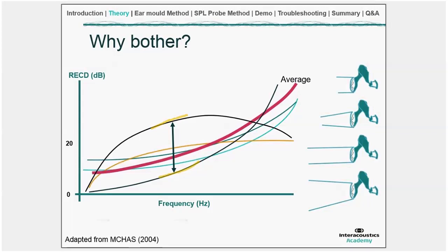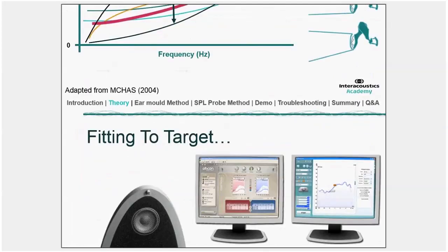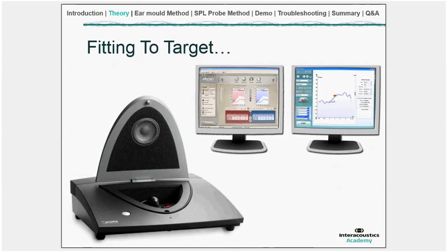RECD measurements are therefore essential, and if you can't obtain one, average data is better than nothing, but individual measurement is needed for an accurate fit. Once the RECD is obtained, the hearing aid fitting process becomes straightforward: place the hearing aid in the coupler inside the test box or on the coupler base, run a traditional real ear aided response, and match target — exactly as you would with a real ear measurement.